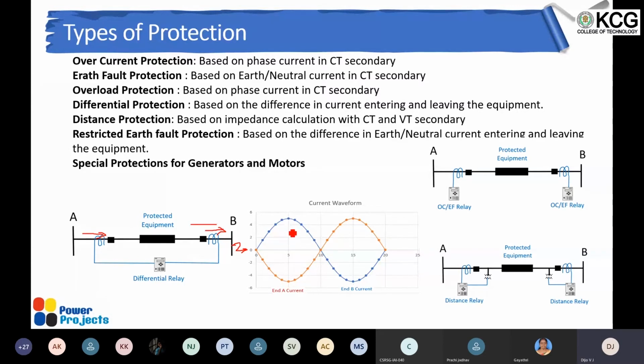That means for an external fault, the protection is not going to operate. But if the fault happens here, then this side CT will change its direction. Based on the value of the current, it will have a waveform like this. If you add the waveforms at any instant, there will be a resultant value. That resultant value will be used for the protection trip. The relay will get this resultant value and operate for an internal fault. For an external fault, it does not operate. That's what we generally call differential protection.